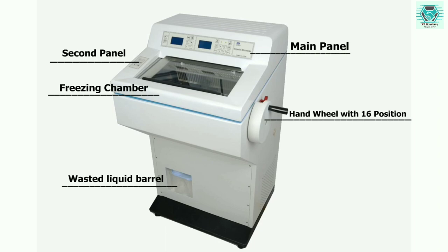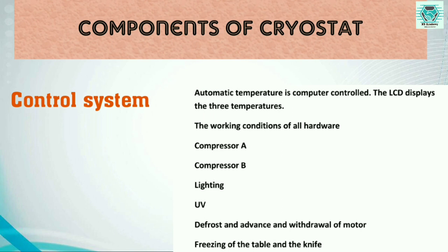Moving to the components: number one is the control system. The automatic temperature is computer controlled. The LCD displays the three temperatures, the working condition of all hardware, compressor A, compressor B, lighting, UV defrost, and the advance and withdrawal of the motor, freezing of the table, and the knife.